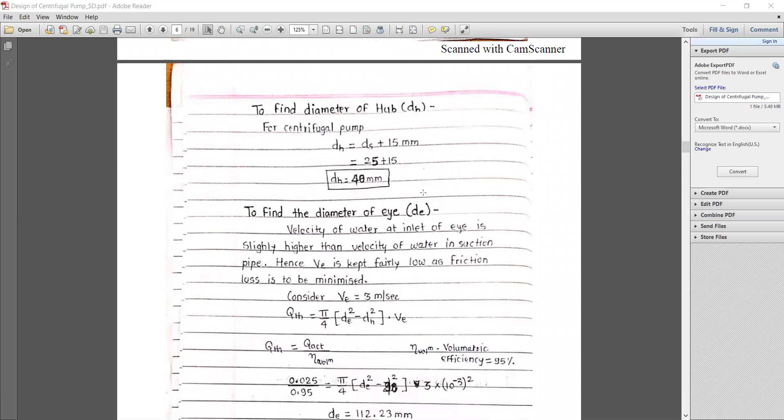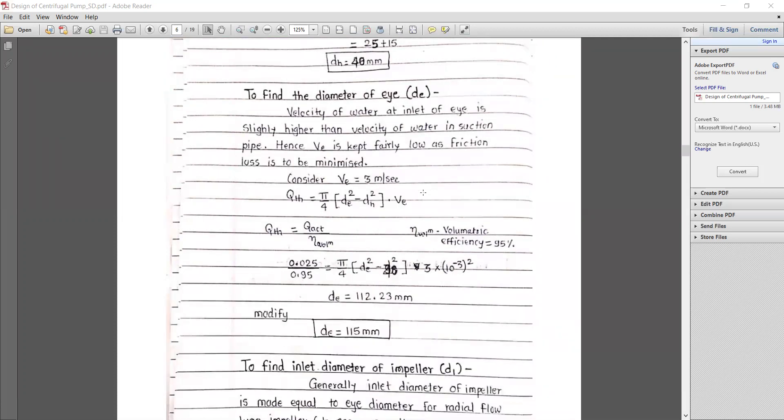To find the hub diameter, using the empirical relation: dh = ds + 15 mm = 25 + 15 = 40 mm. Next, we find the eye diameter. The velocity of water at the inlet eye is slightly higher than at the suction pipe due to the reduced area. To minimize friction losses, the eye velocity ve is kept fairly low at 3 m/s.